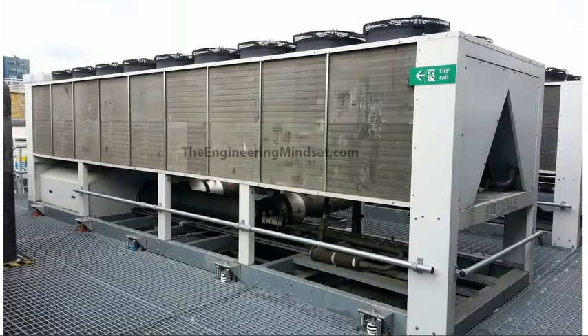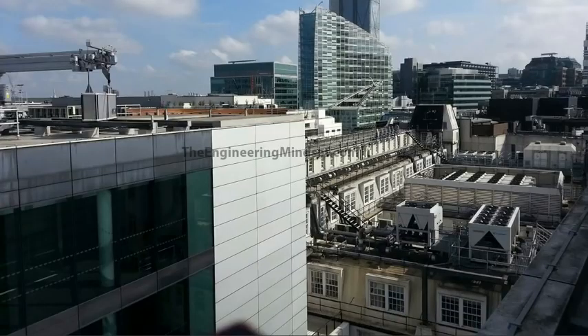They therefore need to be placed outside, so you will usually find them on the roof of a building or maybe on the ground floor, around by the car park, something like this. But if you have a look on the roof, if you can get up to somewhere high and look across some buildings in a city, you'll probably see there's an air-cooled chiller here, there's some more here, there's some condenser units here, there's some more here. They're very common across these kind of small to medium sized buildings, and they're usually on the roof just because of the space requirements.